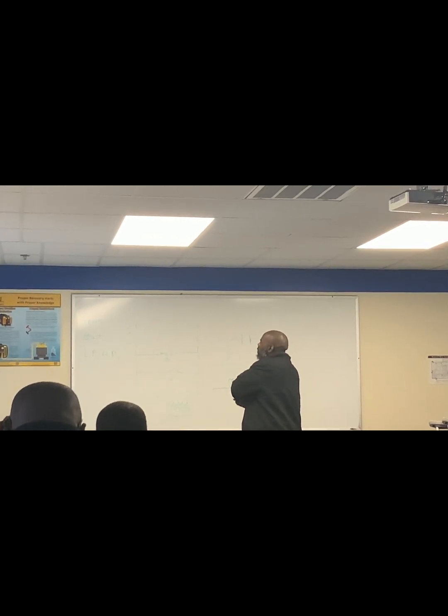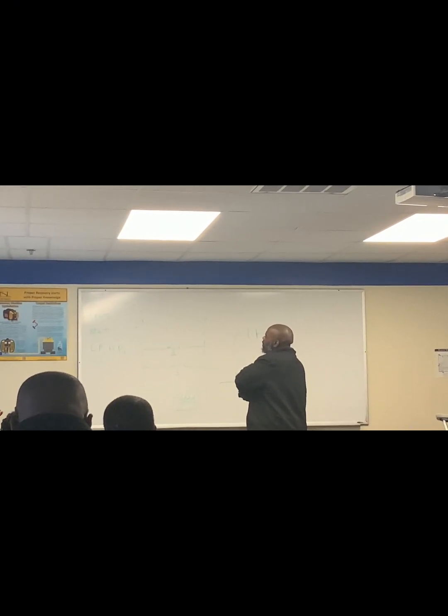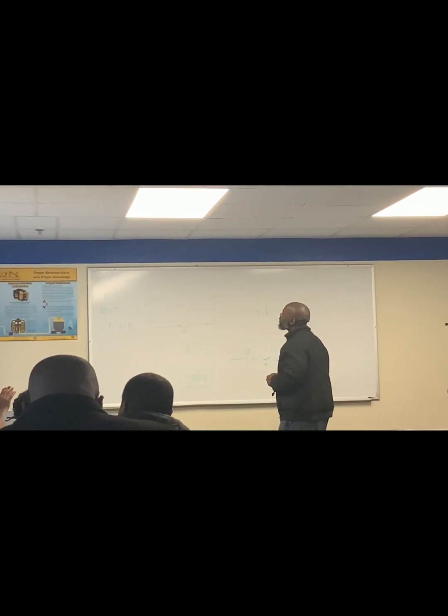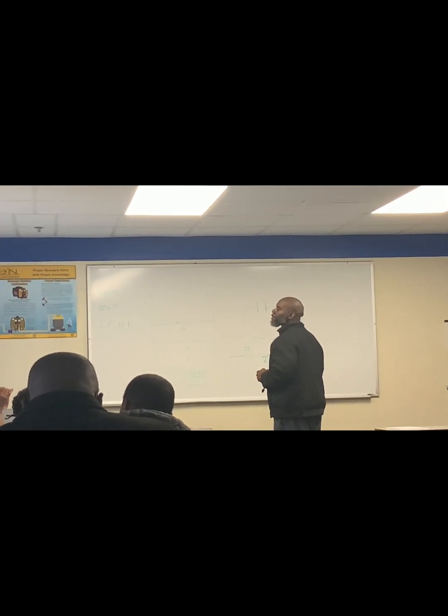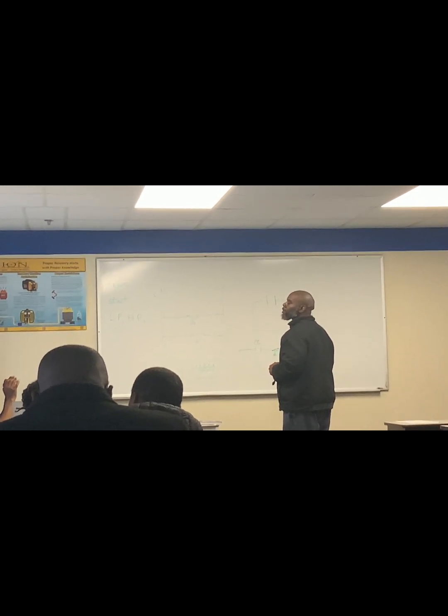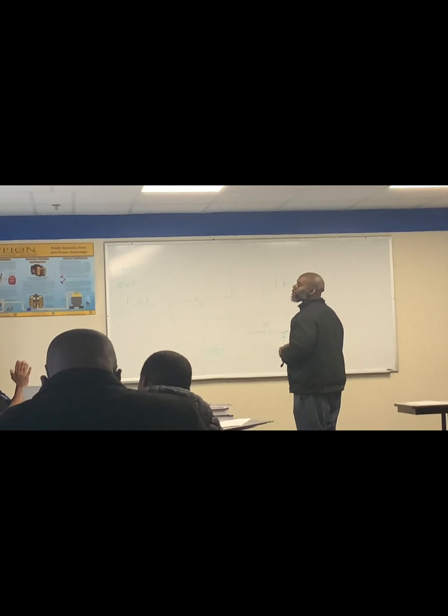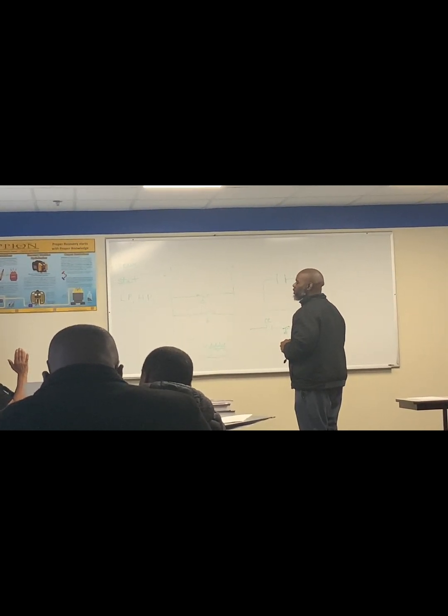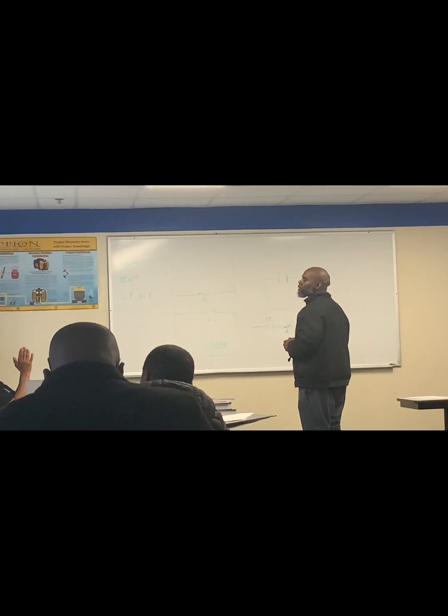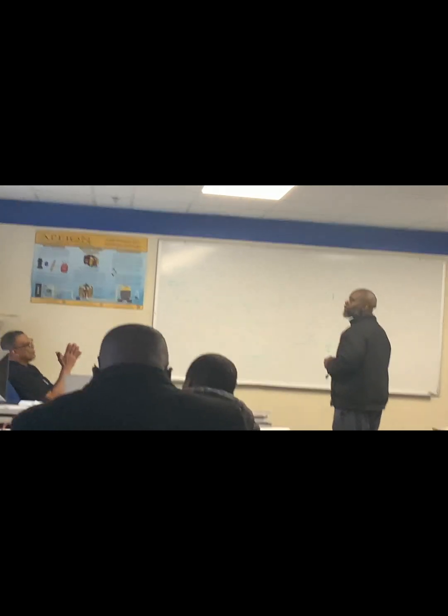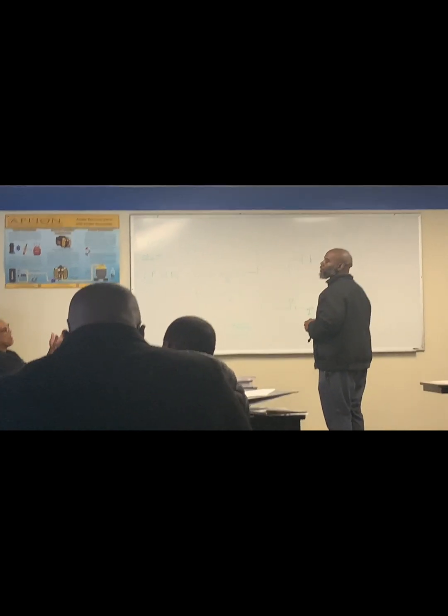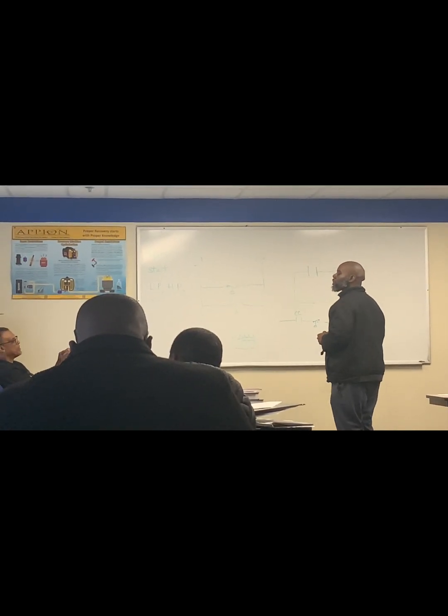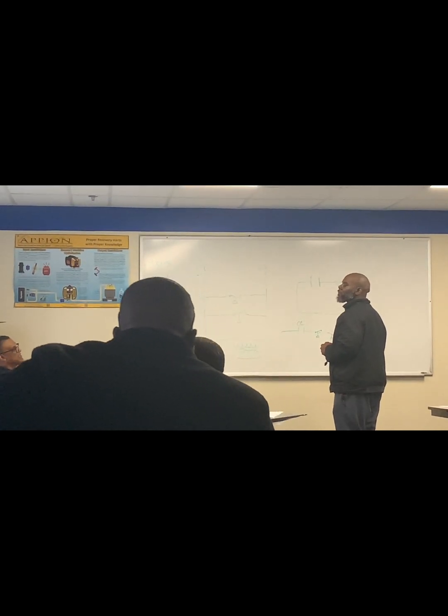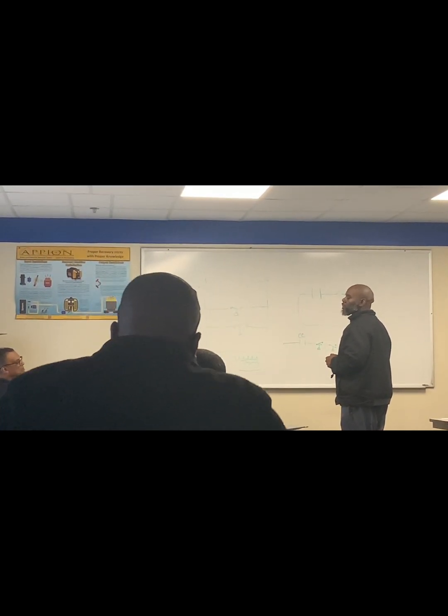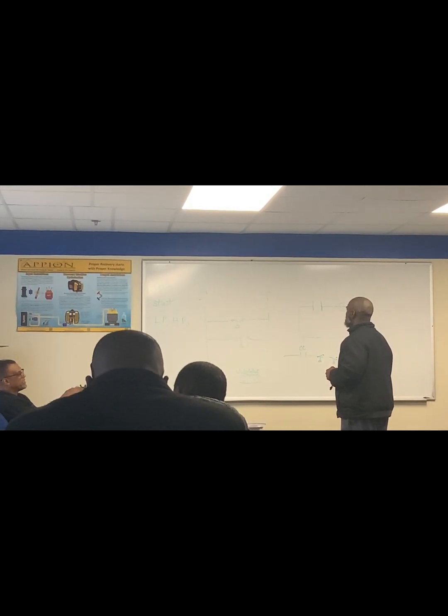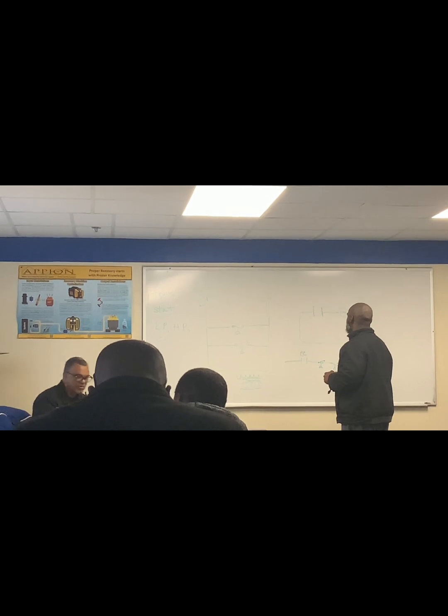That's the part where I'm trying to see how you know low voltage. Once we know low voltage is energized, then line voltage does the work, because they have a shared component, which is a contactor or a relay. Anytime we have a shared component that has low voltage to open and close through a coil, when we close the switch, something's going to run. It's not running by low voltage. The switch is operating, energizing and de-energizing with low voltage, 24 volts. That's what we need to know. So that part for you is okay.